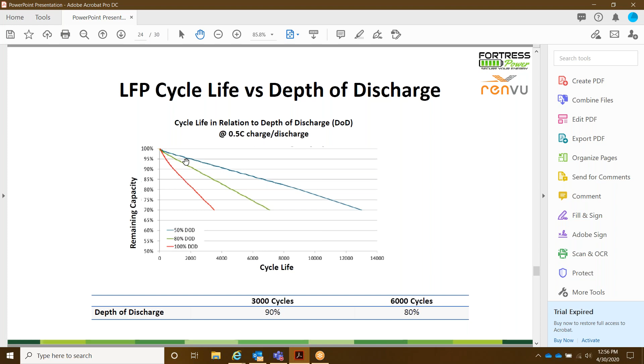But if it's an emergency power, you could really go to 90% or even 100% depth of discharge, depending on what the project calls for. For long life cycles, 80% would make sense since they're cycling it daily, i.e. time of use or off-grid. For someone with emergency power who needs a lot of power a few times a year, 90% depth of discharge or 100% depth of discharge might be the avenue to go. So always be cautious of when people say how many cycles they have, because it really depends on the depth of the discharge, their temperature, the temperature in the area, along with the charging and discharging parameters. So please note this moving forward regarding cycle life along with warranties.